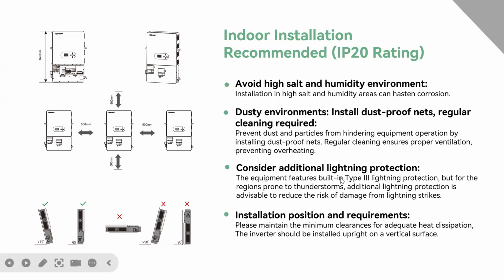And we have to consider additional lightning protection. Normally the SNA 12K is equipped with built-in Type 3 lightning protection, but for regions prone to thunderstorms, additional lightning protection is advisable, to reduce the risk of damage from lightning strikes. As for the installation position and requirements, firstly, we have to leave enough space for heat dissipation, for example, 500 millimeters from the wall or other inverters. And we have to install the inverter upright on a vertical surface to avoid it falling.